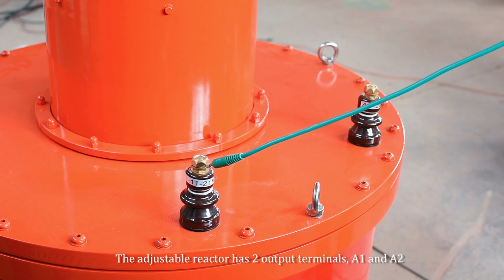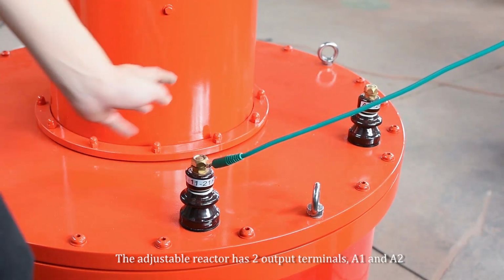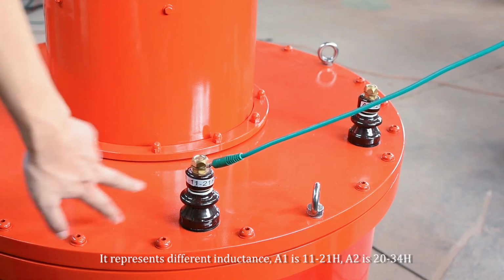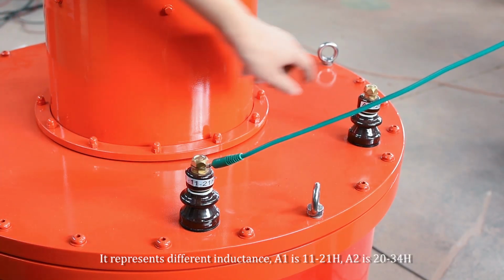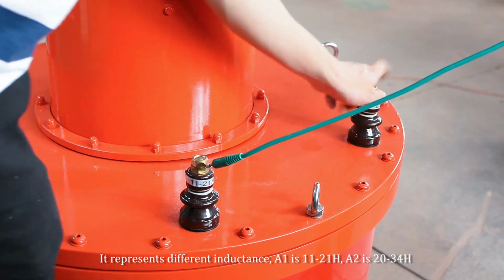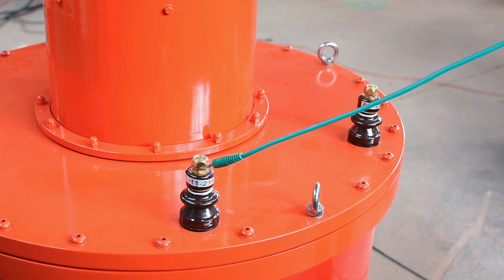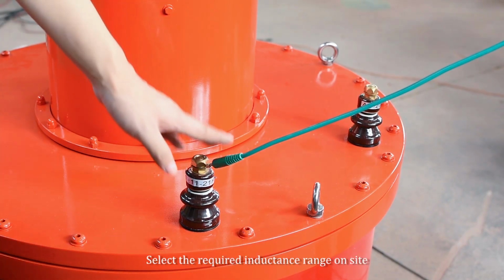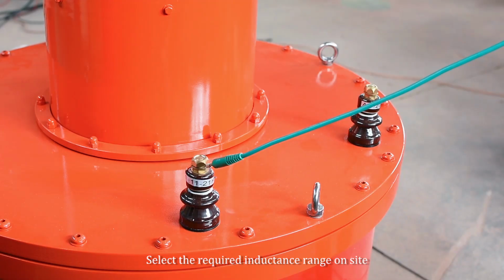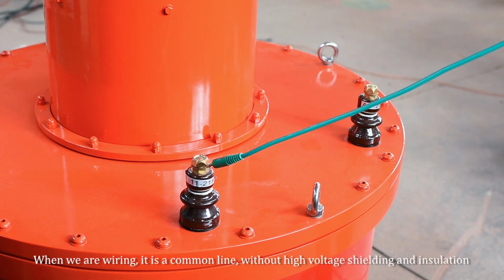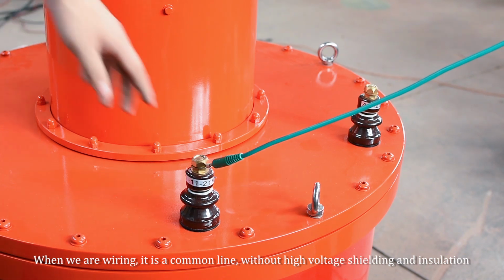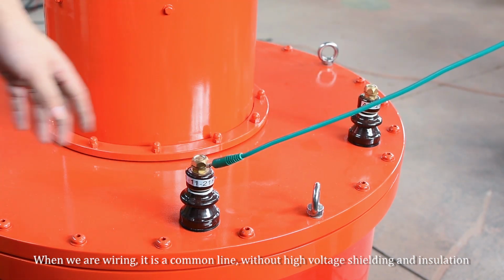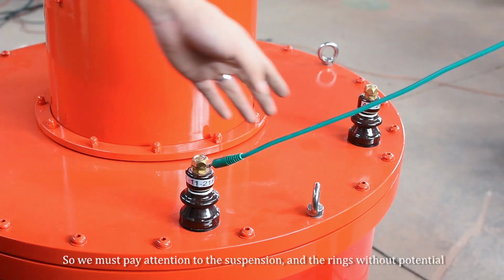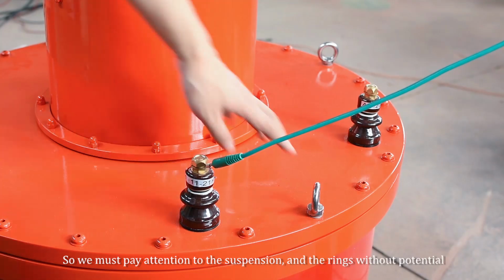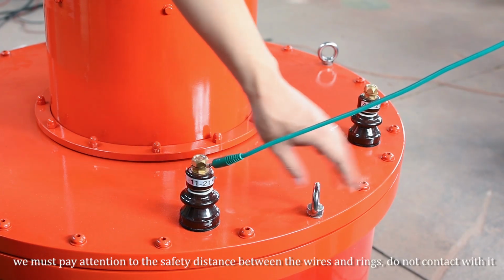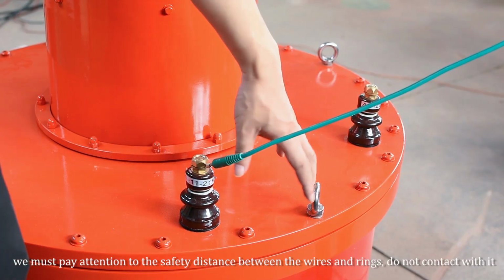The adjustable reactor has two output terminals, A1 and A2. They represent different inductance. A1 is 11 to 21 Henry. A2 is 20 to 34 Henry. Select the required inductance range on site. When we are wiring, it is a common line, without high voltage shielding and insulation. So we must pay attention to the suspension and the rings without potential. We must pay attention to the safety distance between the wires and the rings.